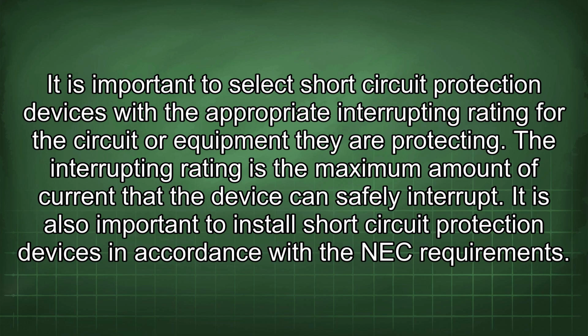It is important to select short circuit protection devices with the appropriate interrupting rating for the circuit or equipment they are protecting. The interrupting rating is the maximum amount of current that the device can safely interrupt. It is also important to install short circuit protection devices in accordance with the NEC requirements.